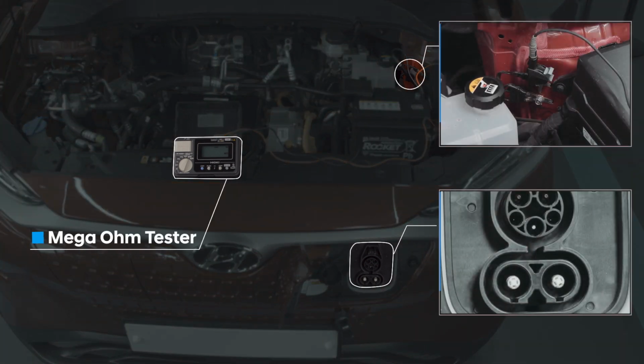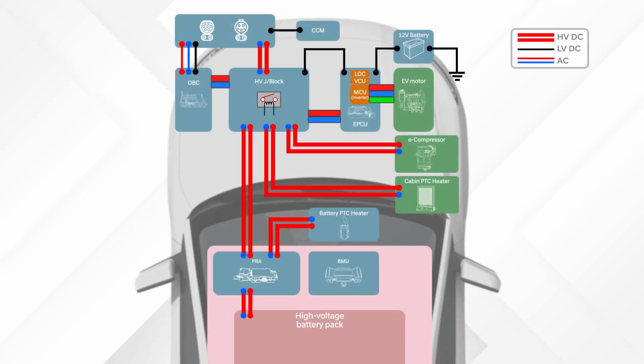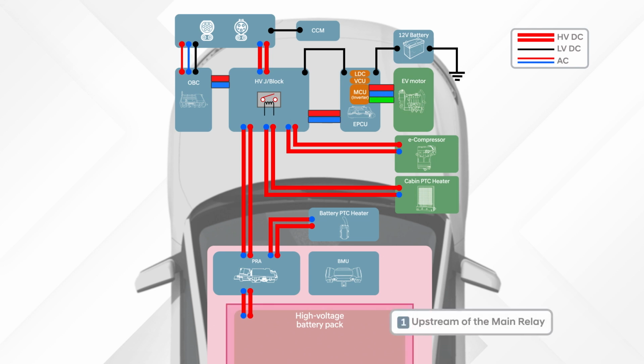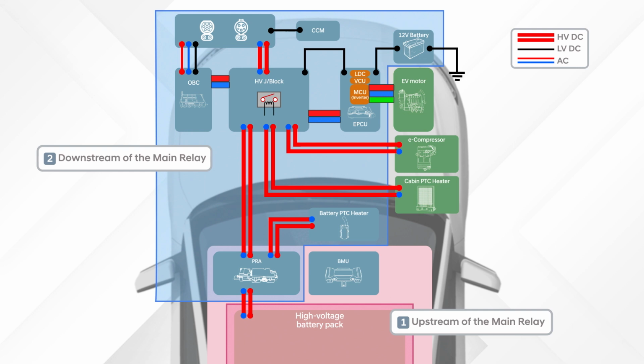Let's now identify the exact location of the defect using a megohm tester. Since the trouble has been identified in the area from the main relay to the high voltage input unit, all areas shown in the figure should be checked.